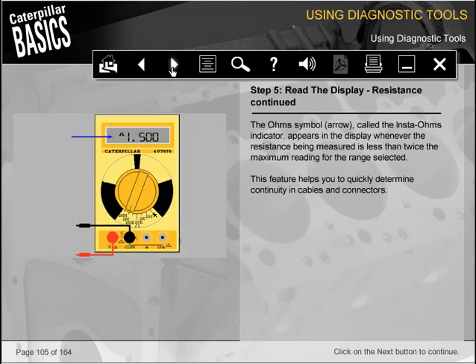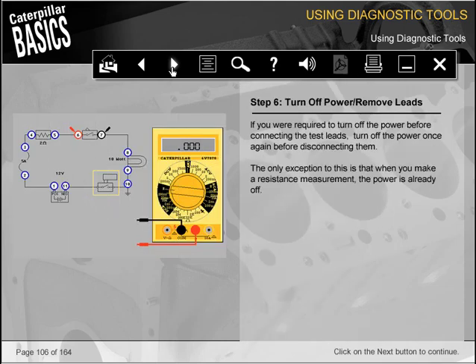The ohms symbol, called the insta-ohms indicator, appears in the display whenever the resistance being measured is less than twice the maximum reading for the range selected. This feature helps you to quickly determine continuity in cables and connectors. If you were required to turn off the power before connecting the test leads, turn off the power once again before disconnecting them. The only exception to this is that when you make a resistance measurement, the power is already off.